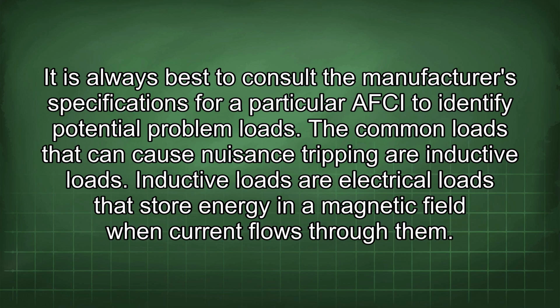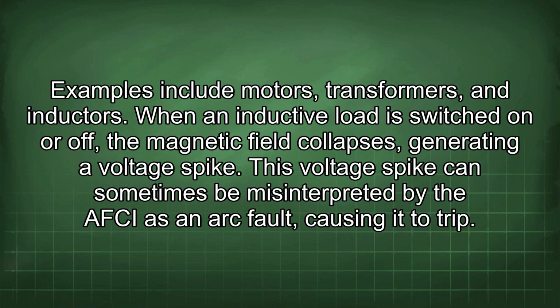The common loads that can cause nuisance tripping are inductive loads. Inductive loads are electrical loads that store energy in a magnetic field when current flows through them. Examples include motors, transformers, and inductors. When an inductive load is switched on or off, the magnetic field collapses, generating a voltage spike. This voltage spike can sometimes be misinterpreted by the AFCI as an arc fault, causing it to trip.